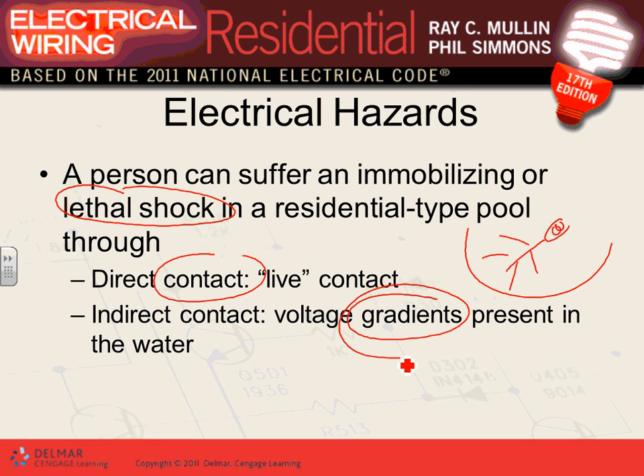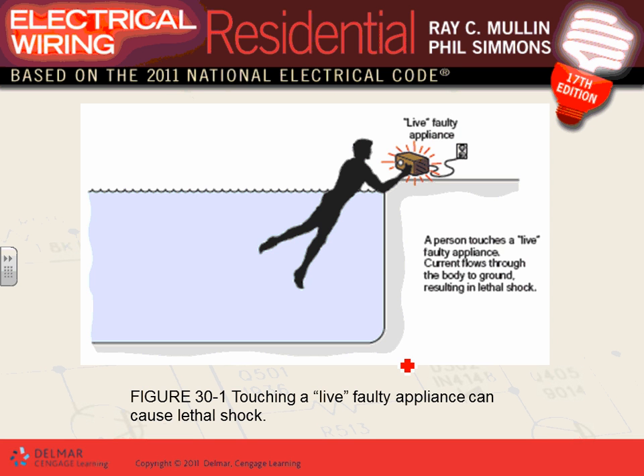So almost everything energized, lights, receptacles, has to be at least 6 feet away from the inside of the swimming pool or spa or hot tub. By doing it this way, they minimize the chances that you're going to be grabbing on something energized. Remove it, move it away. Don't put the receptacle a foot away from the swimming pool, right? So that's number one. Number two, voltage gradients. Voltage gradients. Here's the shock.